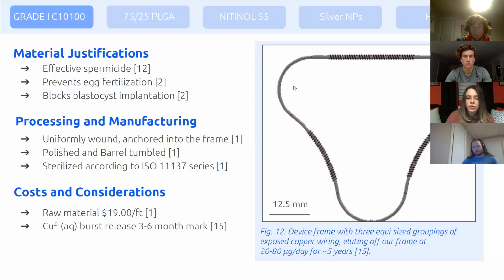The wire has a uniform diameter of 0.255 millimeters. The proximal end of the wire will be anchored into the frame and uniformly wound. The distal end will be tucked into the frame, and the entire frame and the copper will be polished and barrel tumbled to prevent sharp edges in utero. The copper will be sterilized at 40 kGy of gamma radiation, and the wiring itself is relatively inexpensive, but the toll it takes in utero is not insignificant. The burst release effect of copper during the first 6 months of device lifespan is a significant deterrent.